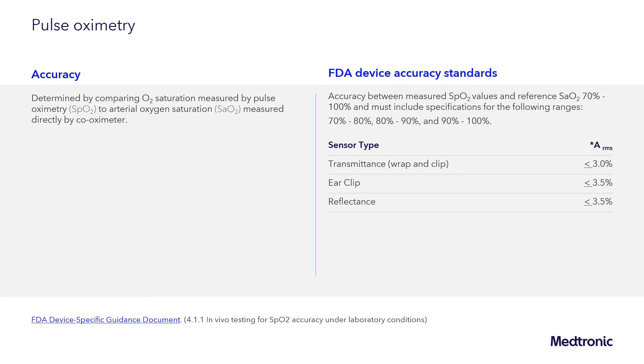ARMS approximates the mean absolute deviation between SpO2 and SaO2. The difference between a direct measured saturation and that measured by the pulse oximeter must be less than or equal to 3 percent for transmittance wrap and clip style, and less than or equal to 3.5 percent for ear clip and reflection sensors.